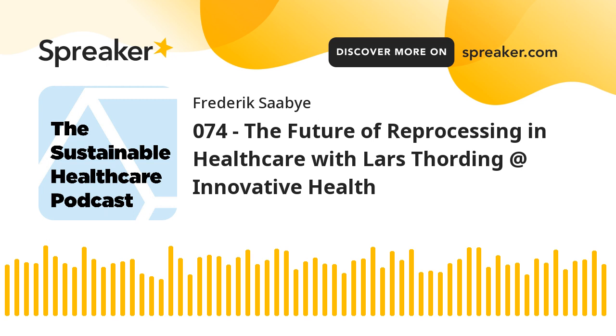As a reprocessor, I'm going to look at, is that catheter really so bad, so poorly designed that it can't be reused? And sometimes it is. Other times, the material integrity, the functionality, and so forth are actually so good that it can be safely reused one more time. In other cases, it's 3 more times. In cardiology, we really don't reuse these devices more than 3 times, because the risk of failure gets too big. Yeah. Exactly. We're a super conservative industry when it comes to safety. Patient safety is one that cannot be compromised.